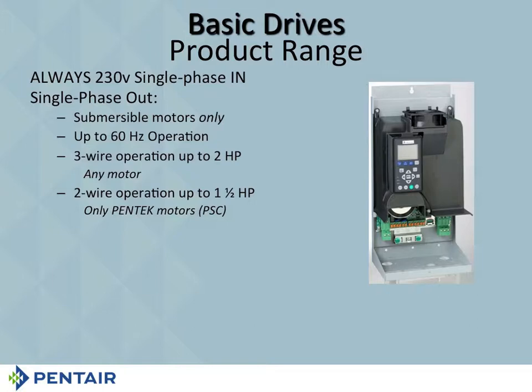But more importantly, it must be a PSC motor. PSC stands for permanent split capacitor. And the reason that we're making that designation is because Franklin doesn't use that. They use a split phase motor on their 2-wire, and because you're using a split phase motor, it doesn't work with this drive. So you have to use either our motor or the Gould's motor, which is also a permanent split capacitor.